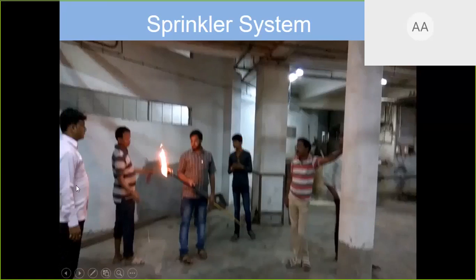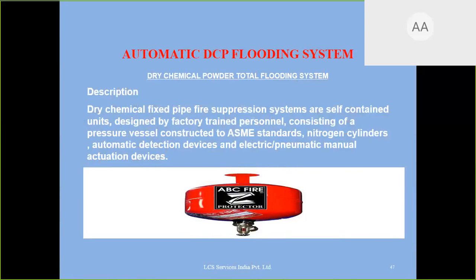So that was the sprinkler. Now there is an automatic DCP flooding system which is installed in some panel on the top, which also acts at 68 degree temperature. There is a DCP powder, dry chemical, fixed pipeline suppression system, a self-contained unit designed by factory trained personnel. It consists of a pressure vessel constructed to ASME standard, nitrogen cylinder, automatic detection devices, and electric, pneumatic or manual operation. There is no electrical line, no air line, nothing is required. It senses the temperature and the powder comes out automatically.